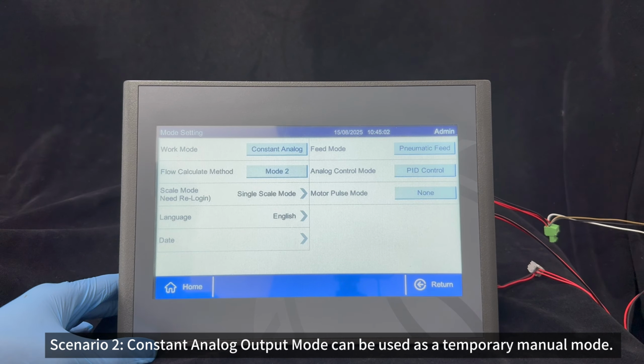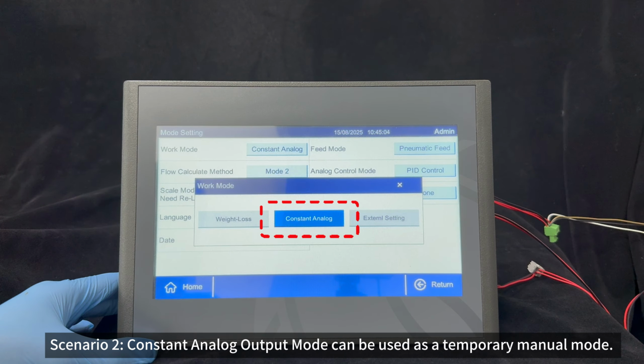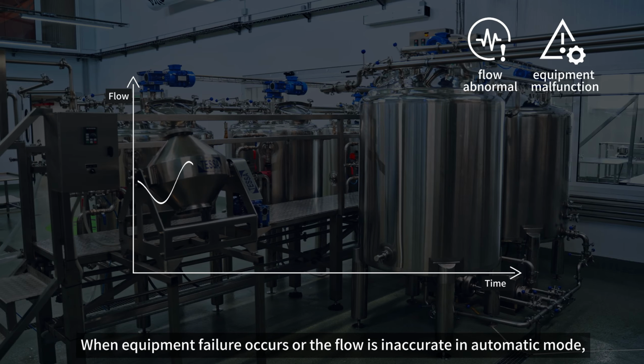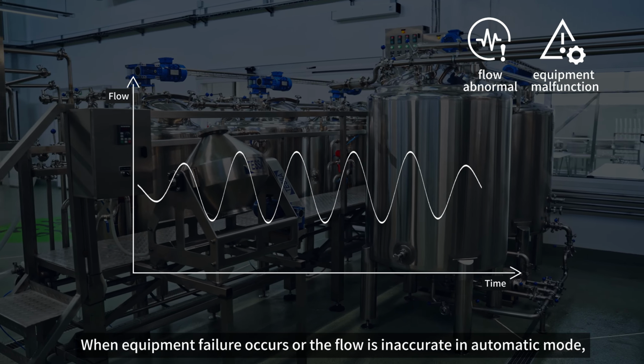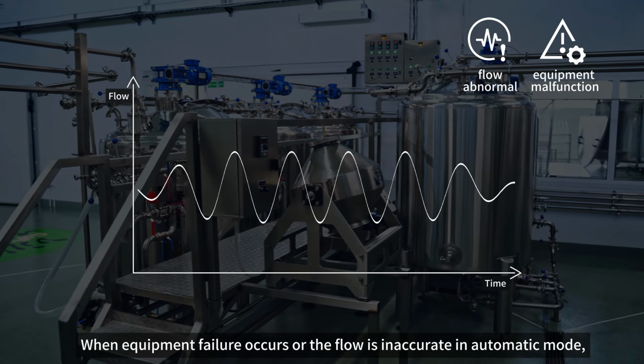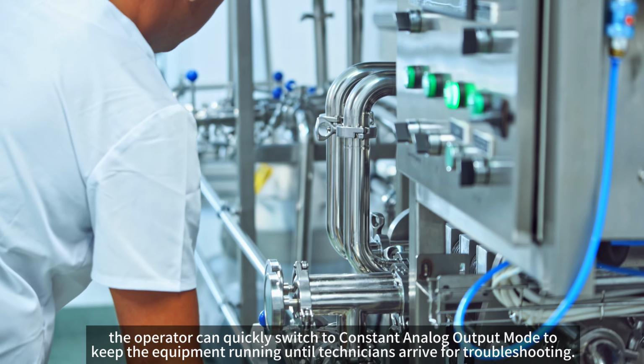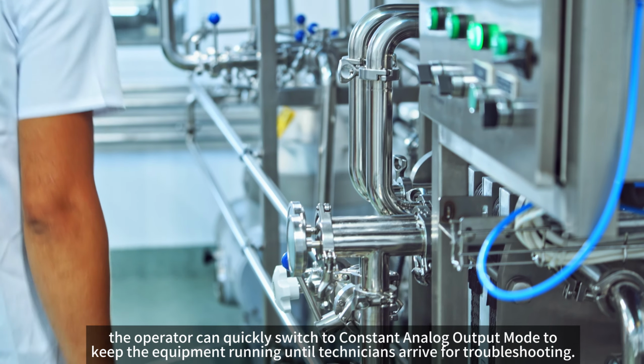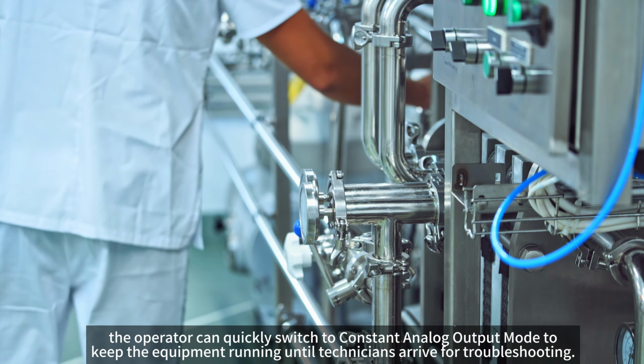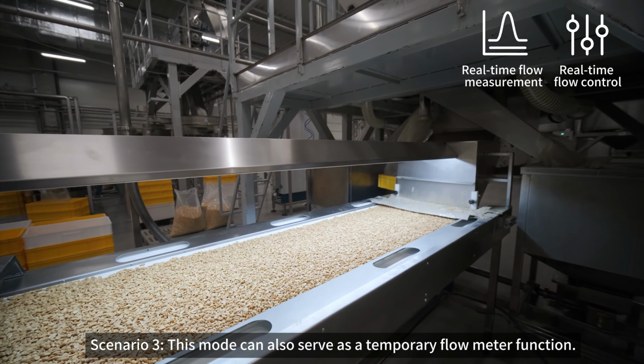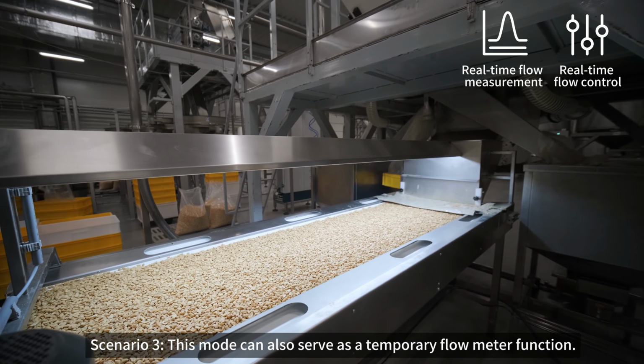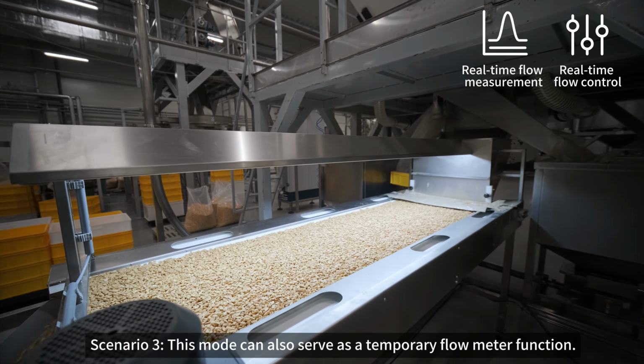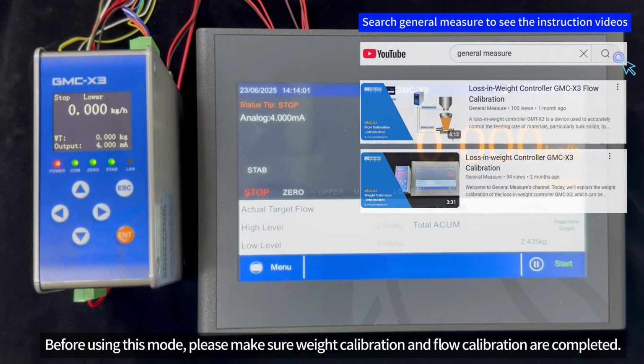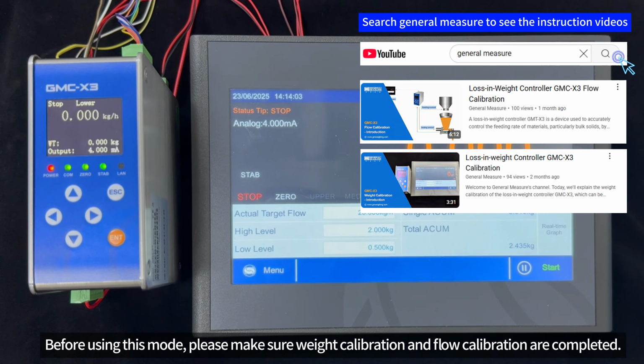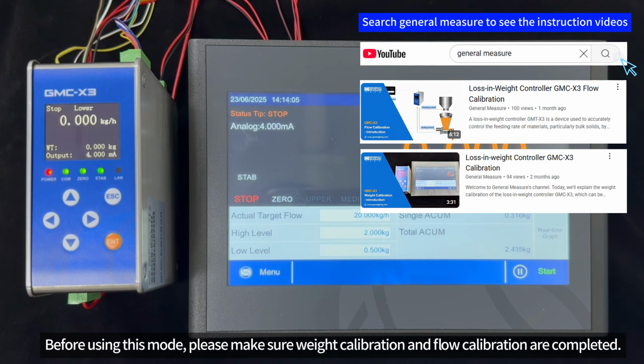Scenario 2. Constant analog output mode can be used as a temporary manual mode. When equipment failure occurs or the flow is inaccurate in automatic mode, the operator can quickly switch to constant analog output mode to keep the equipment running until technicians arrive for troubleshooting. Scenario 3. This mode can also serve as a temporary flow meter function. Before using this mode, please make sure weight calibration and flow calibration are completed.